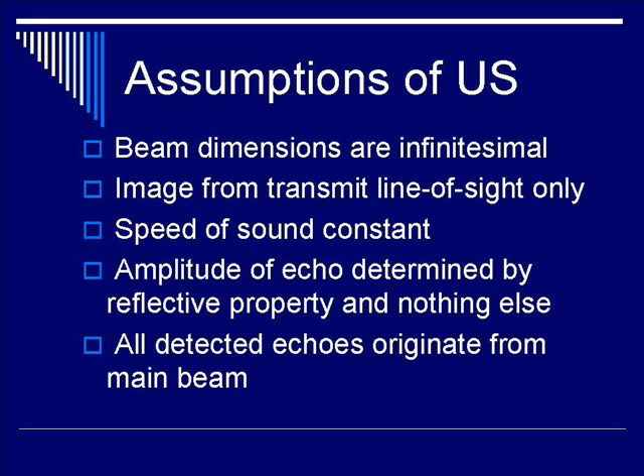Let's go through some of the assumptions of ultrasound scanning. Number one, we assume that beam dimensions are infinitesimal — that is, the x, y, and z directions can be resolved down to very minute dimensions. Two, ultrasound image only comes from the transmit line of sight. Three, speed of sound is constant. Four, the amplitude of the echo is determined solely by the reflective and intrinsic property of the reflector. Finally, that all detected echoes originate from the main beam.